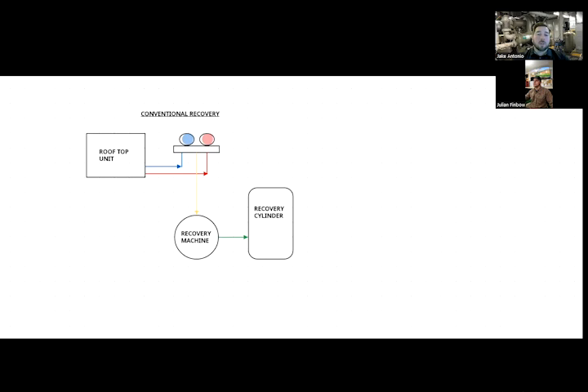I have used a smaller recovery machine on a chiller, and it's just not as fast because the pump is a little bit smaller. I've used a smaller recovery machine and moved 500 pounds of liquid refrigerant in 8 hours. Compared to one of the bigger chiller recovery machines, I could move anywhere from 1,000 to 2,000 pounds in a day, just depending on the configuration and the tanks and stuff like that. So just a little bit different of a process and a little bit of a different time frame too.